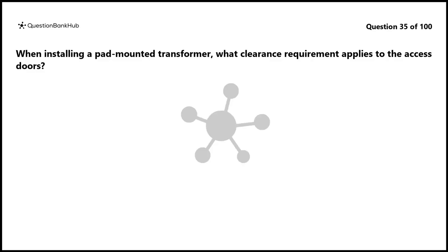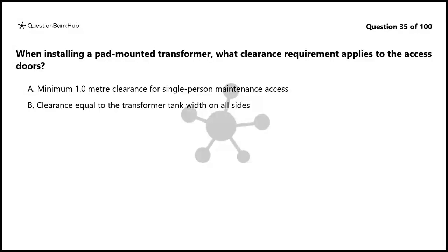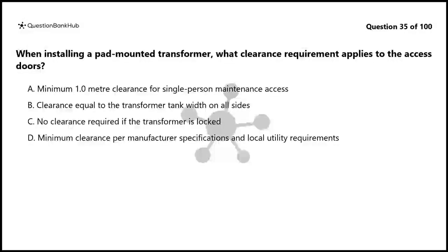Question 35. When installing a pad-mounted transformer, what clearance requirement applies to the access doors? A. Minimum 1.0 meter clearance for single-person maintenance access. B. Clearance equal to the transformer tank width on all sides. C. No clearance required if the transformer is locked. D. Minimum clearance per manufacturer specifications and local utility requirements.